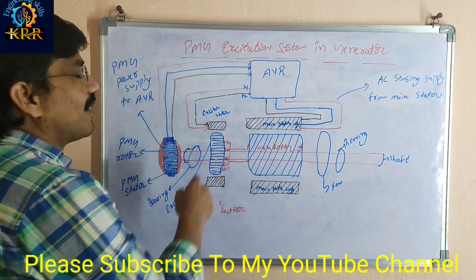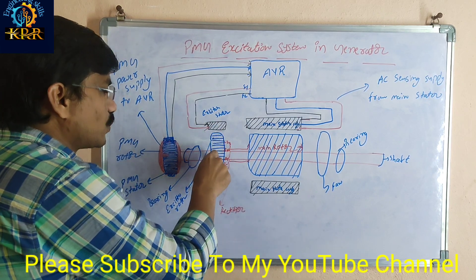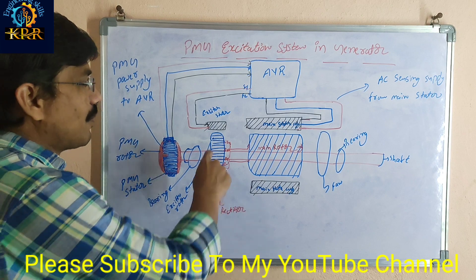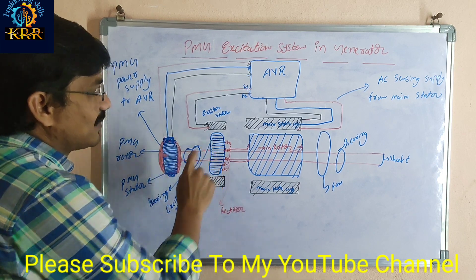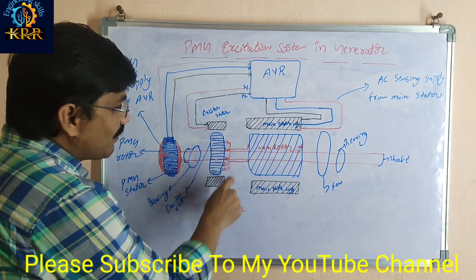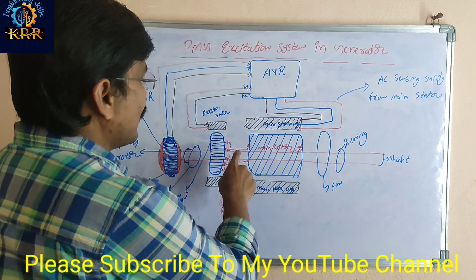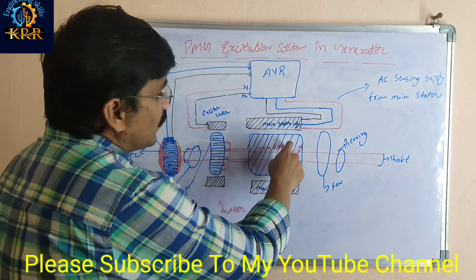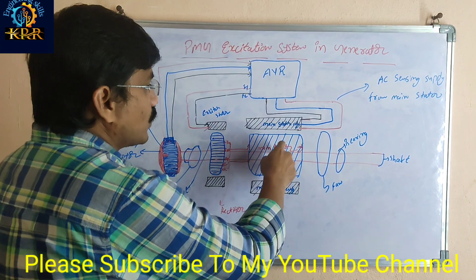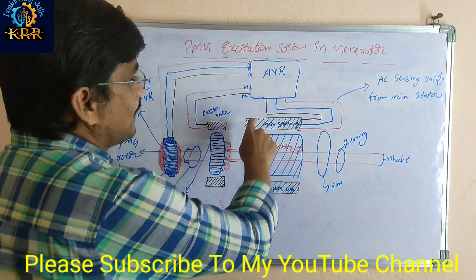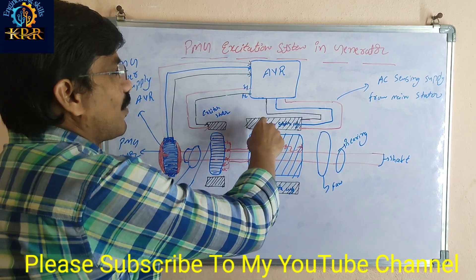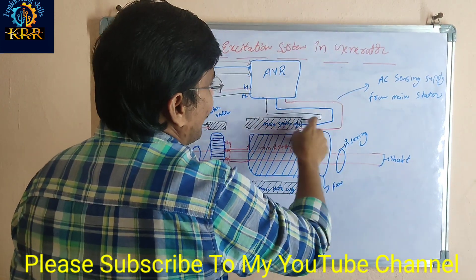The exciter stator winding receives power and current flows through it, generating flux. This flux cuts through the exciter rotor, inducing EMF and generating AC power. This AC power is converted to DC power by the rectifier. The DC power passes through the main rotor winding, generating flux that cuts the stator winding and induces EMF, generating output power.